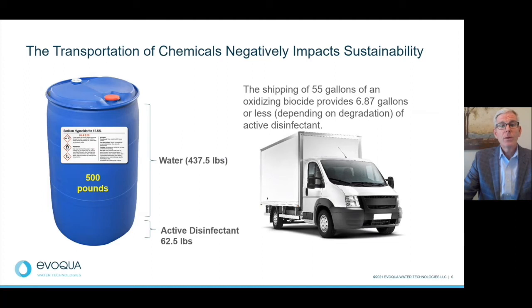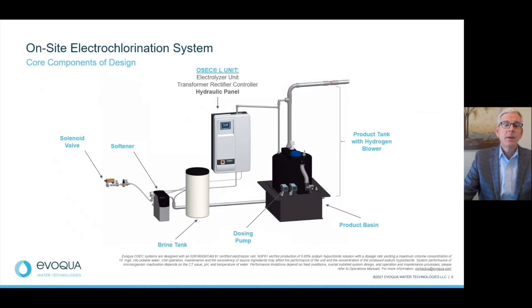Now, one way to improve this equation is to generate the sodium hypochlorite at your data center. And you can do this via Evoqua's OSEC system. OSEC stands for on-site electrochlorination. OSEC works by converting a brine solution that is made from water and salt. The brine solution is pumped through an electrolytic cell, which converts the brine into a low concentration of chlorine, roughly a 0.8% concentration. So instead of transporting the water on a truck that has a carbon footprint, you use the water that comes out of the tap.